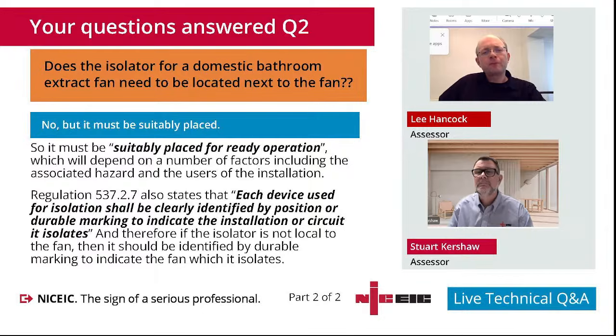Obvious. Yeah. While we're on the subject, Sam, can I extend on a little bit of information there? It's something I come across quite often when we're out doing the assessments with contractors. We all know how to fit these. Predominantly, in a lot of cases, it's a 3-core and earth going to the fan isolator, and then from the fan isolator, another 3-core and earth going up to the fan itself. And for many, many years, contractors have just been using 3-pole isolators, just the standard ones.